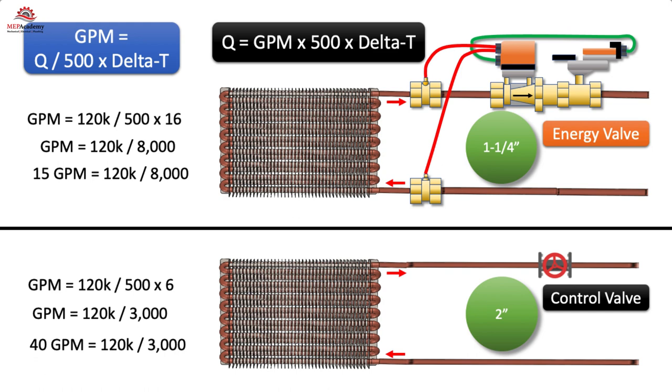We can look at the difference between maintaining delta T with an energy valve and the traditional system. We converted our formula to solve for GPM. Using a heat load of 120,000 BTUs per hour, or 10 tons, we get 15 GPM if the energy valve is maintaining the delta T at a set point of 16 degrees. The traditional system has slipped to a 6 degree delta T, requiring 40 GPM to get the required heat transfer. This additional GPM causes an increase in pump energy and would require larger piping. The size of the piping for the energy valve system would be 1 1/4 inch, while a traditional system would require 2 inch to match the same heat transfer quantity.